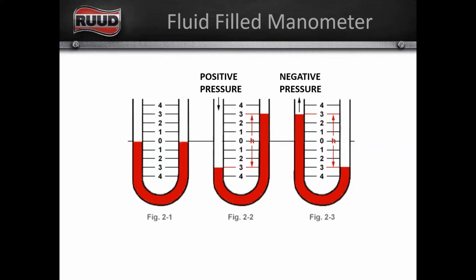In figure 2-2, we have a pressure tap in the positive air pressure stream, which would be our supply. That positive pressure, the pressure of the air moving through the ductwork and pressing against the sidewall of the duct, remember, that's our static pressure pressing against the sidewall of the duct. That pressure moves through our tap into our piece of tubing and pushes that water down, and that is measured in inches water column. So in the diagram here we have 3 inches water column on the positive side. So we've got our 0, plus 1, plus 2, plus 3. That's 3 inches water column on our positive side.